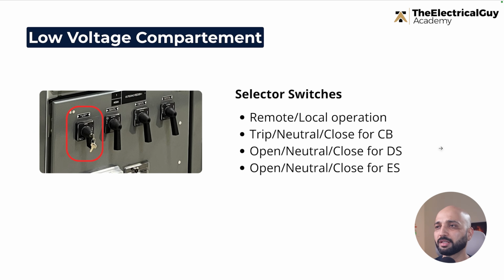Then we have selector switches. You see all these are selector switches. With the help of these, you can select different conditions for circuit breakers and disconnectors. Let us see some common examples. The first and very commonly seen selector switch is remote or local operation. You get two types of operation that you can perform. One, you can give a remote command from the SCADA system and the circuit breaker will trip. That's what we call remote.